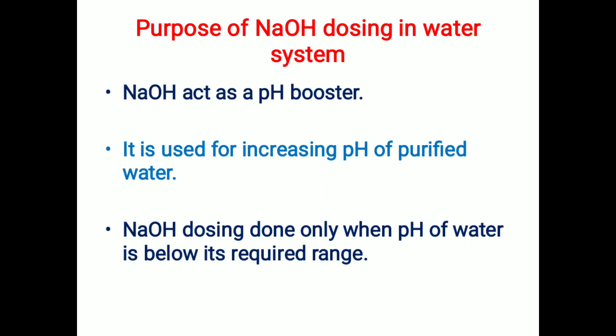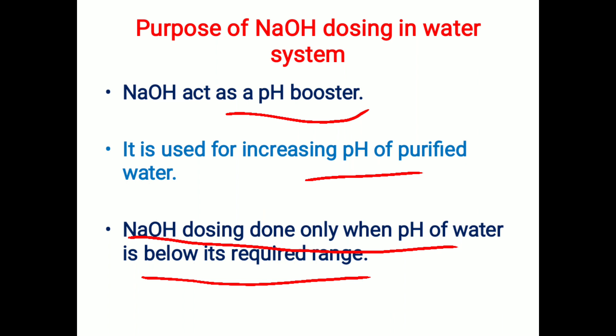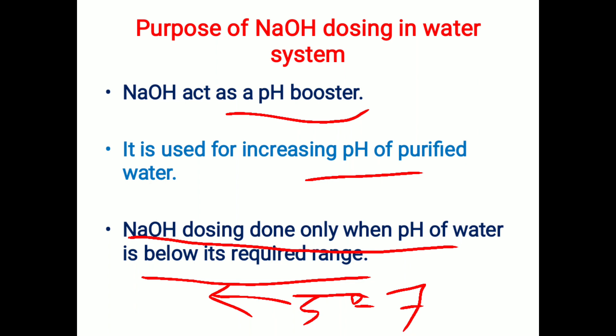First, we'll see the purpose of sodium hydroxide dosing in a water system. Sodium hydroxide acts as a pH booster — it is used for increasing the pH of purified water. Dosing is done only when the pH of the water is below its required range, which is 5 to 7 for purified water in pharma industries. When the pH goes below 5, we start sodium hydroxide dosing to bring the pH back into the required range of 5 to 7. NaOH is an alkaline solution used for increasing pH.